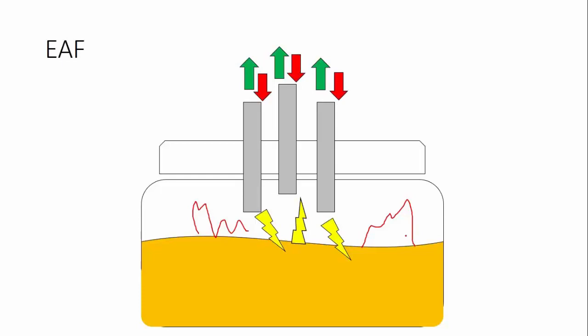So as the melting process continues, the electrodes can go up or down depending on the part of the cycle. At the beginning, the electrodes have to be near the metal, and then as the metal starts to get molten, the electrodes can go up or down depending on the power that should be delivered or how much heat the furnace can resist.